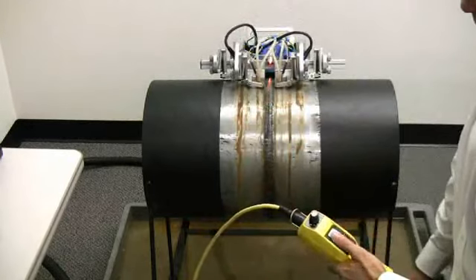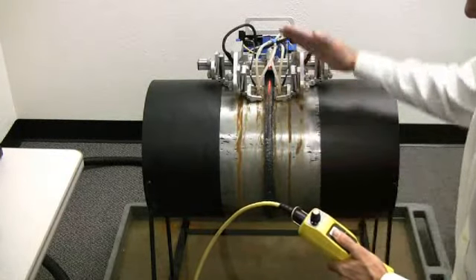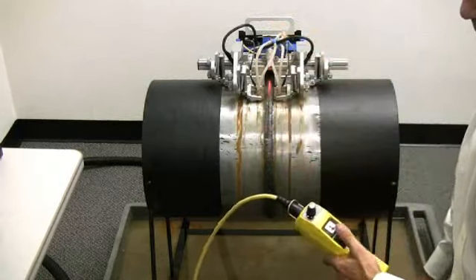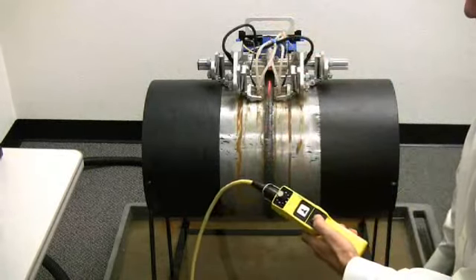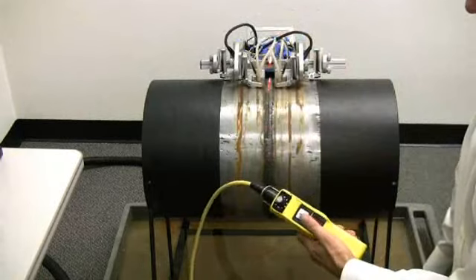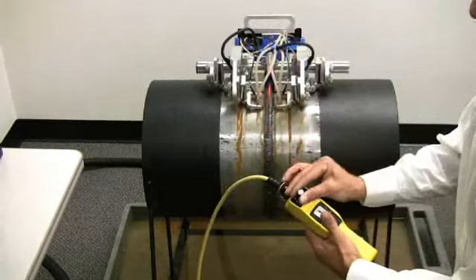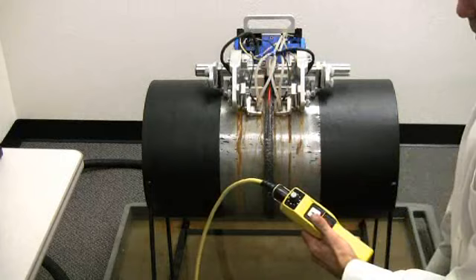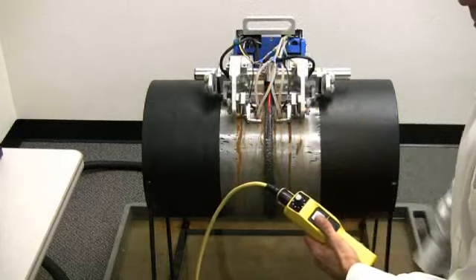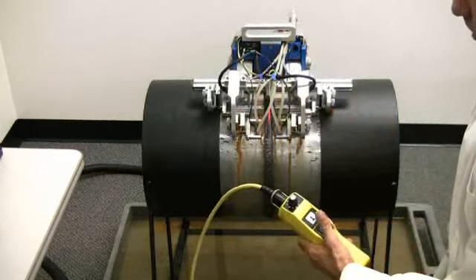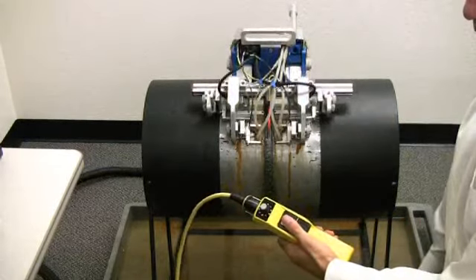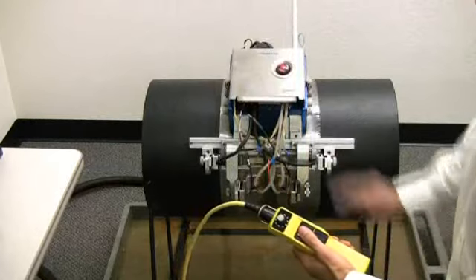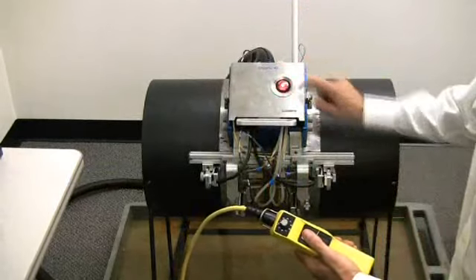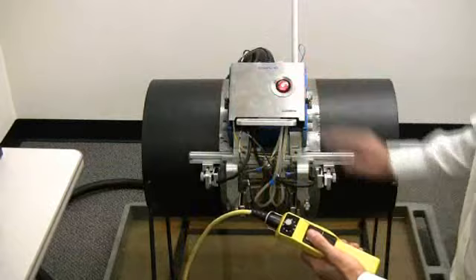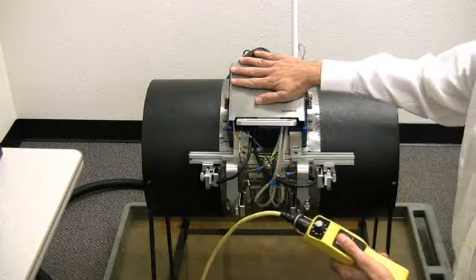We can jog the scanner in 2 directions. It's encoded in both directions, or we can hold the button down 1 time for constant motion control. We can change speeds during the acquisition to maximize our scan time as long as we don't exceed the acquisition rate of the instrument. In addition to the remote control, we also have an emergency stop built directly onto the scanner for CE compliance and completely disables power to the scanner.